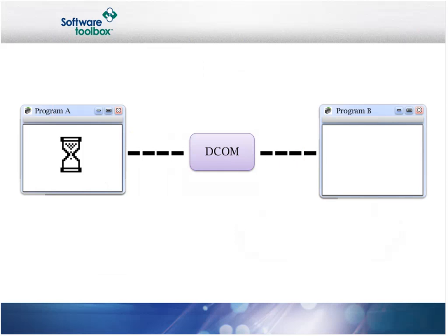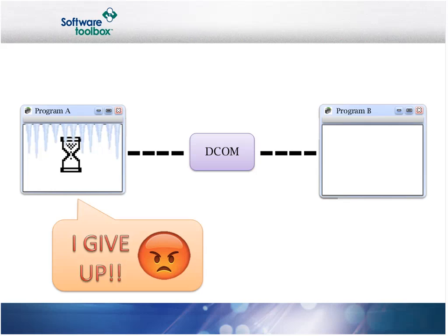Normally, it's not a problem if you're locally connected to your OPC server and all is well. However, you've seen the downside of this if you've ever used DCOM and had your client HMI appear to freeze or lock up while trying to get data from a remote PC. That freeze happens because your client has made a call to the remote server and is waiting on a response. It would be one thing if the requesting application could just give up at a reasonable time, but it's not really possible, even though I know every OPC developer out there wishes they could just have their client give up.